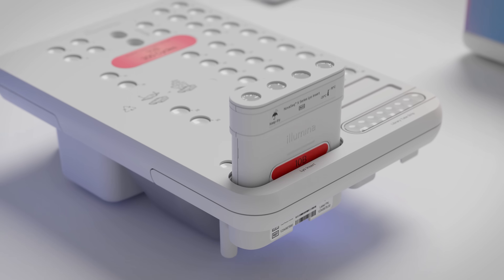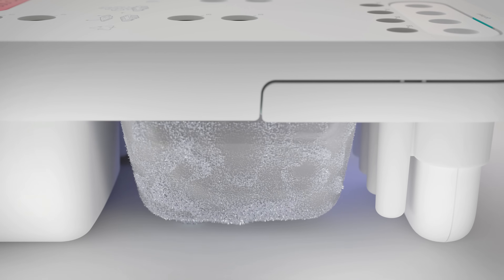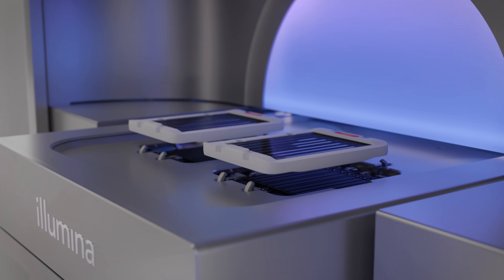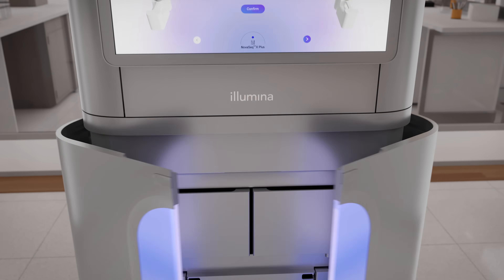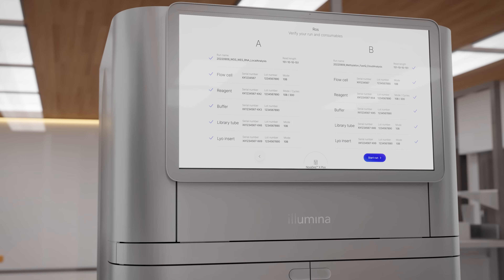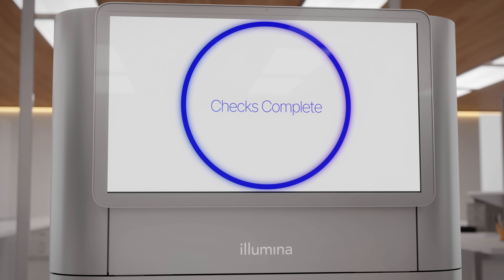Handling is much easier with lightweight reagents, buffer cartridges, and waste containers. Load-and-go reagent cartridges feature thaw windows to visually verify that reagents have thawed completely. The system will lead you through the process of run preparation and reagent loading — the light bar and drawers will guide you through the steps. The instrument will check that all RFID-encoded reagents have been loaded properly, and sequencing will begin after pre-run checks, minimizing the chance of user error and ensuring compatibility of reagents.